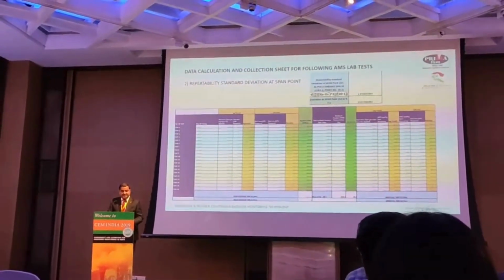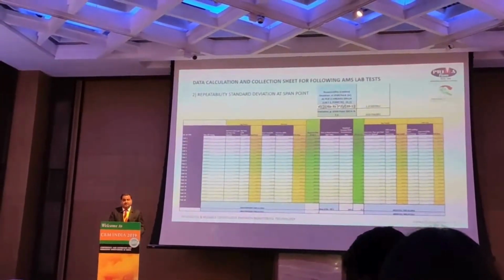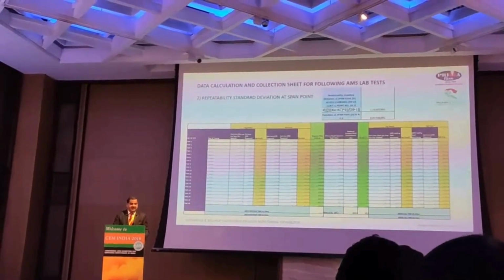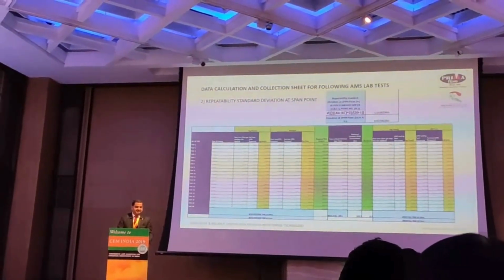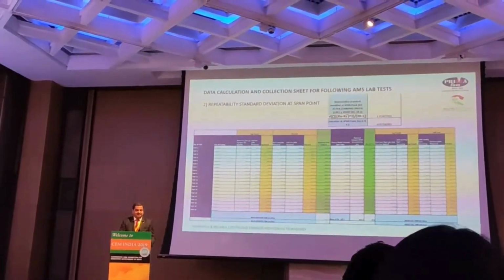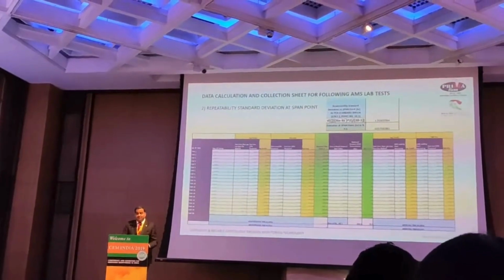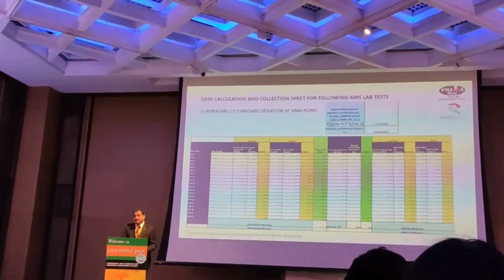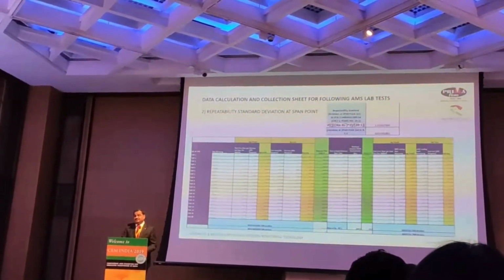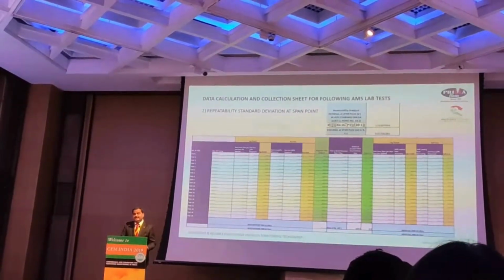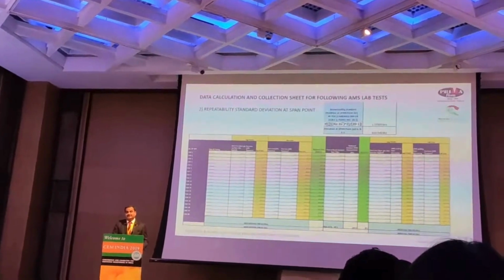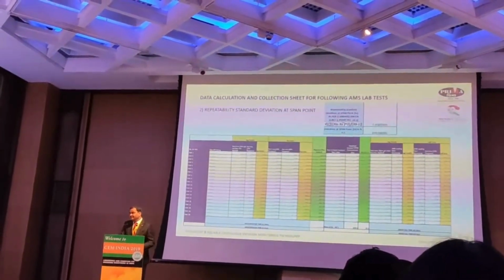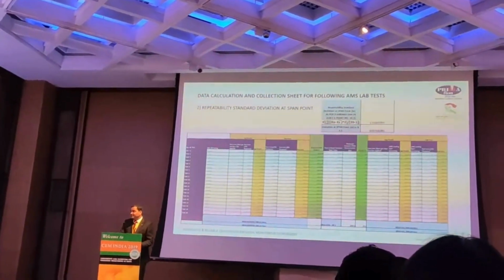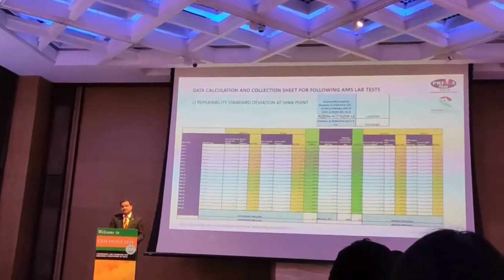Further, we go with the repeatability standard deviation at span point. Again, we got the deviation at span point in percentage of full scale coming to 0.05. We are still trying to get better here. It's not only the sensing part, the electronics also have to be very effective in generating the analyzer output.